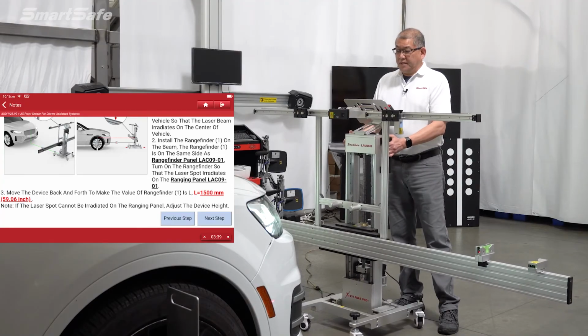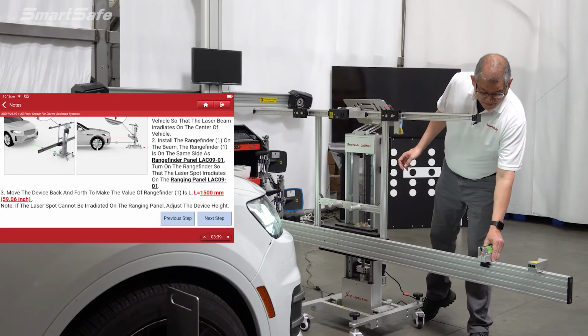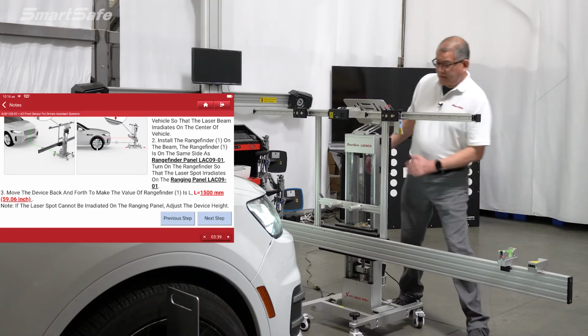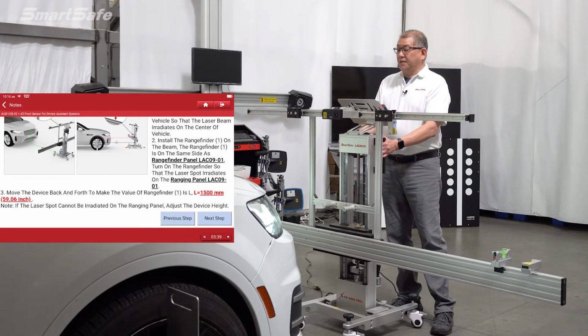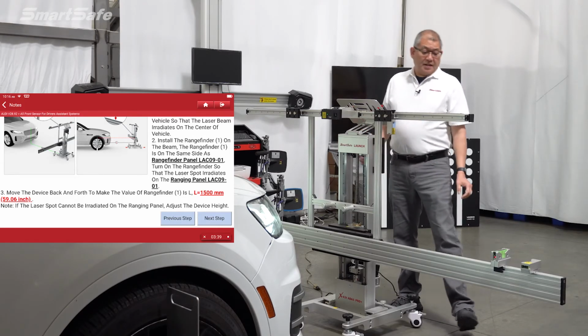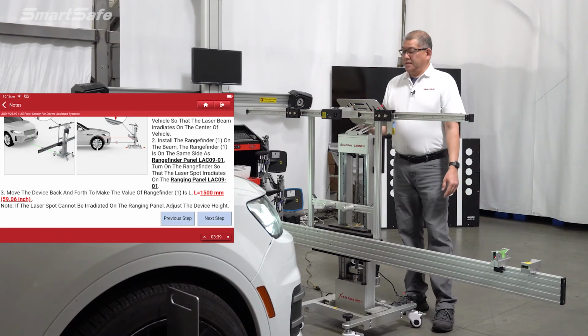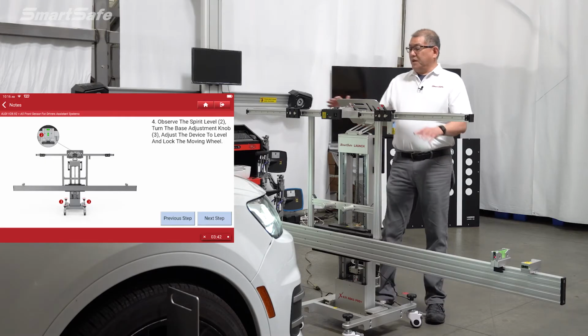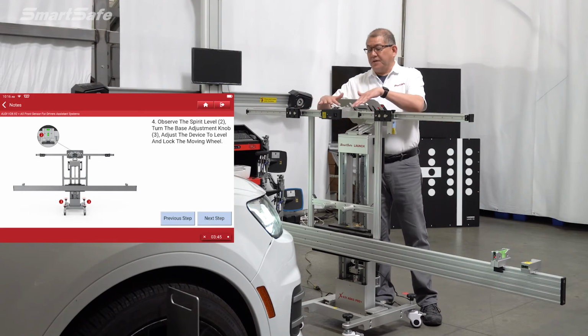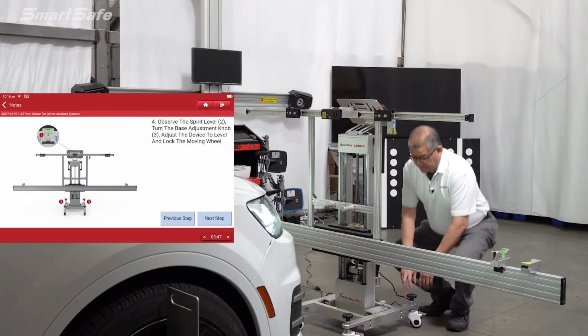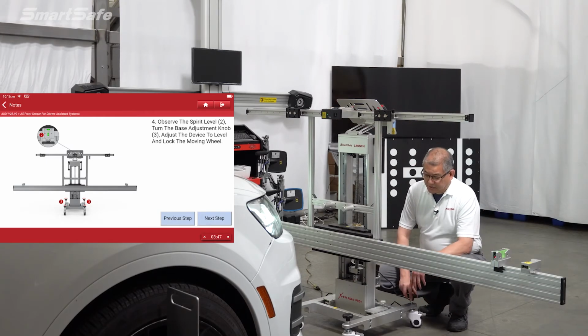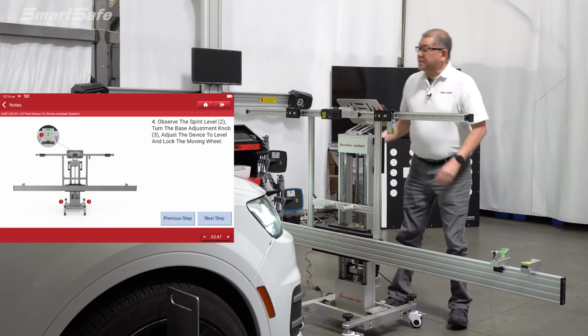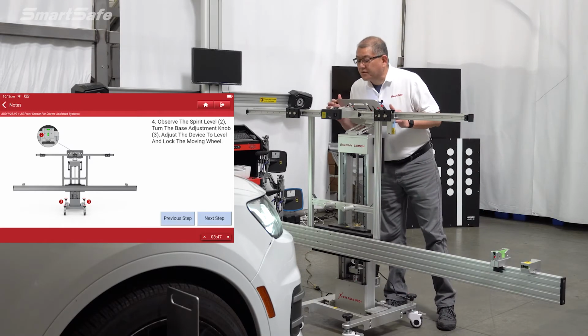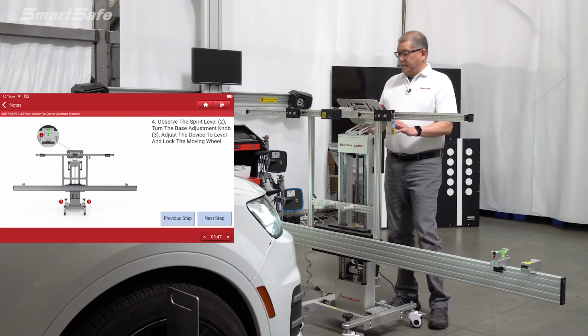Get that squared away. All right, and we're just at about 1500 here. So we'll go ahead and move on to our next step. We want to make sure that our frame is level. So we have bubble viewfinders here, and I'm going to go ahead and take a look. Looks like we need to make a little bit of an adjustment, and that will be done by these knobs that are on the casters. So I just need to increase this side a little bit, and actually we're right on. So we'll go ahead and go to the next step.